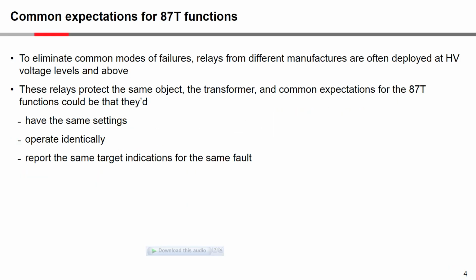When we look at protection application, in what the utilities do, very often, if they're going to have two main protections, a system A and a system B, they require that these relays come from different manufacturers. They have their reasons for that, to eliminate common mode of failure, etc.